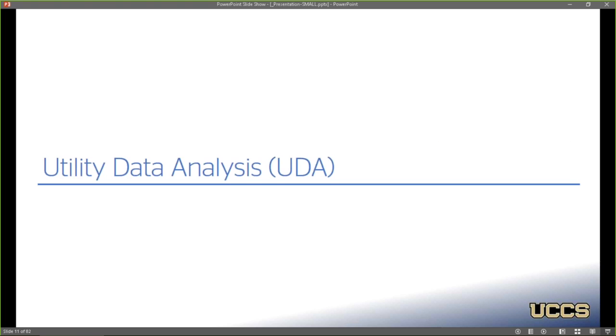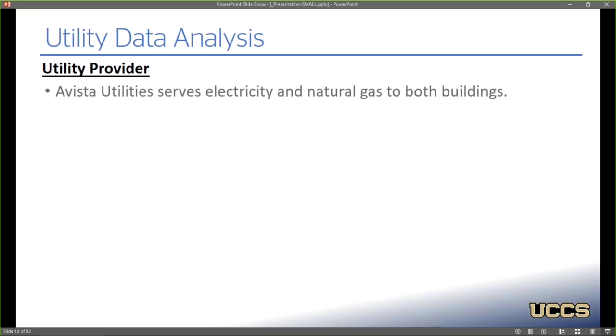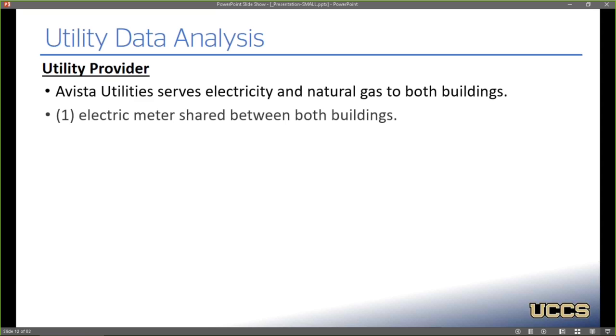So usually the first step when you're doing an audit is to look at the utility data and see what kind of conclusions you can draw just from a high level analysis. Avista Utilities serves electricity and natural gas to both buildings, but there is a common electric meter that's shared between both buildings, which means you can't actually separate the usage between them. They are, however, independently metered on the gas side.